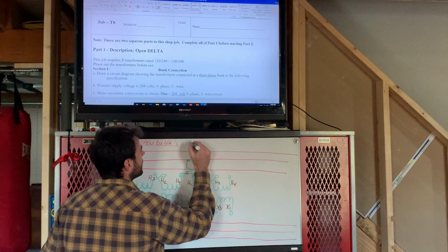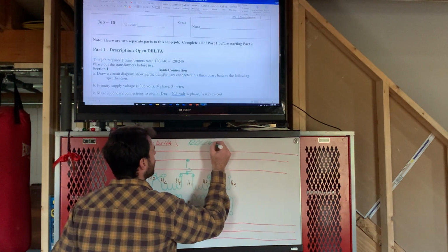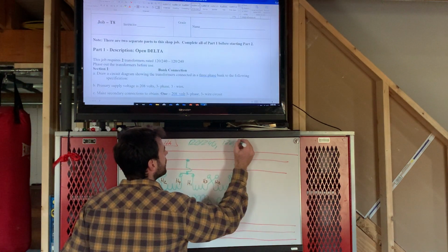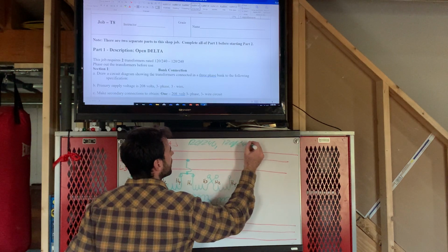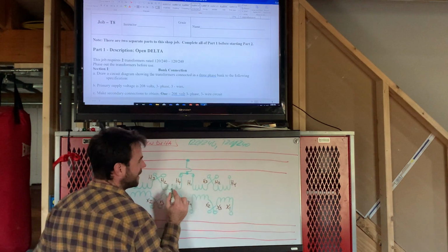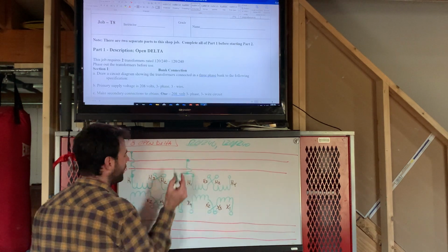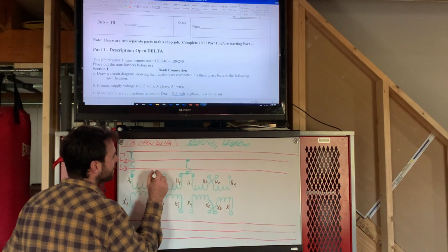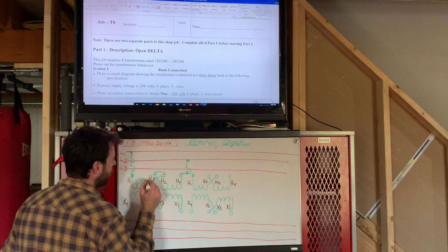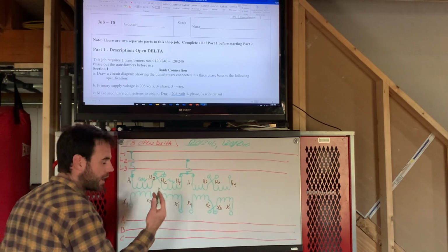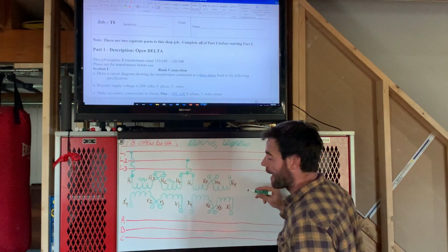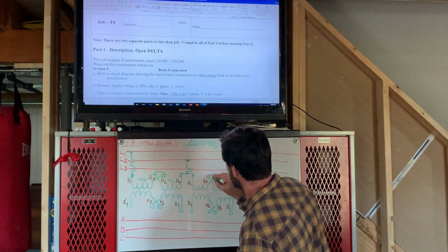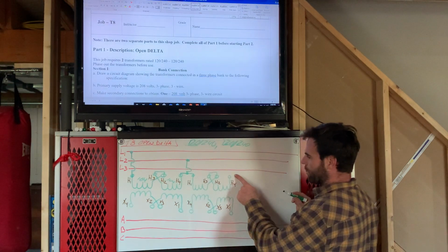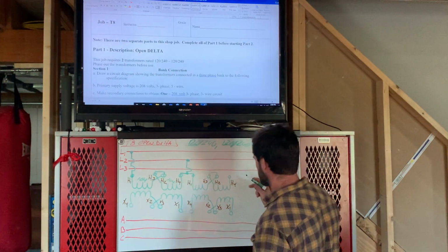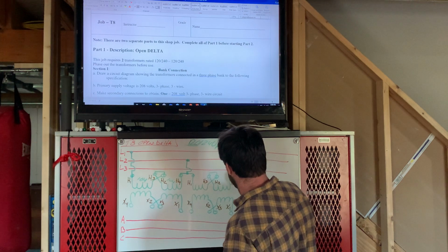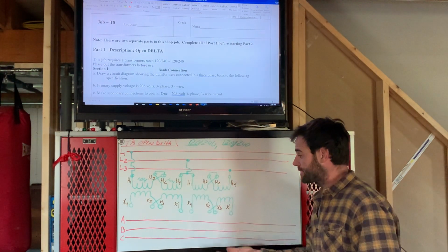These transformers are rated 120/240, 120/240. The highest voltage we can put in an individual coil is 120 volts. So we're going to put these in series to get 240, 240. All right? Same thing over here, except now we're going to put these in series again, H3 to H2, except we're going to bring this H4 up to line 3. Basically the same connections on the secondary side.